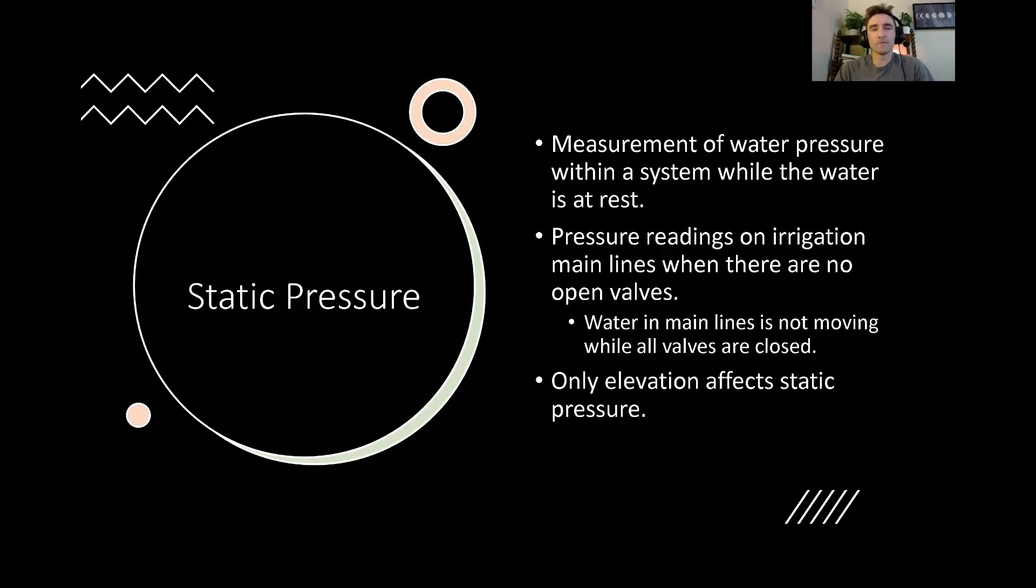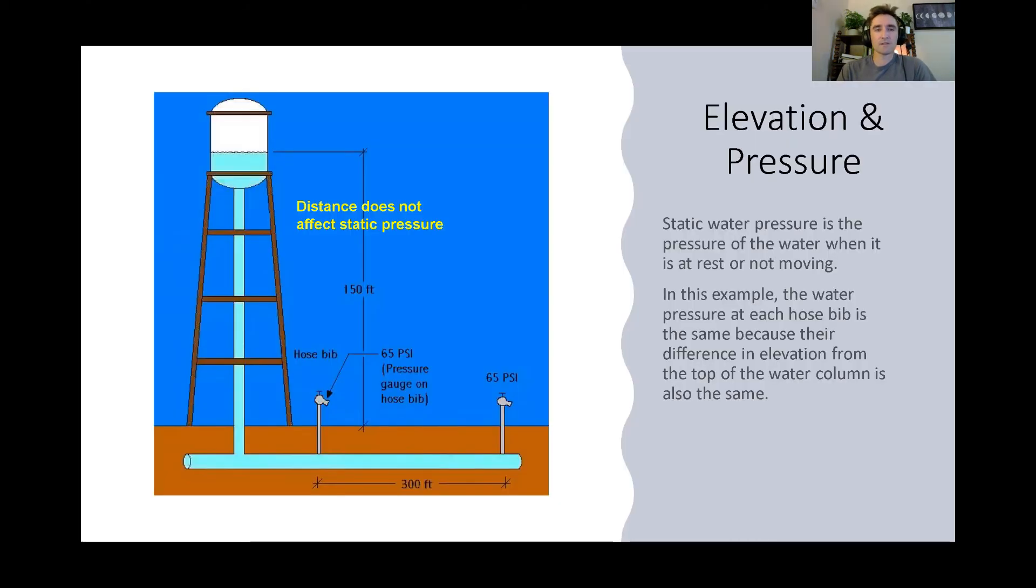Everything that we've been measuring so far is known as static pressure, meaning this is the measurement of water pressure within a system while the water is not moving, while the water is at rest. When we take pressure readings and the water is not moving, the only influence of change in water pressure will be elevation. That's the only thing that's going to have an impact. Now, when we talk about static water pressure, one thing that kind of may not make sense, it's not intuitive, is that the distance has no effect. The only thing that changes your pressure is your elevation.